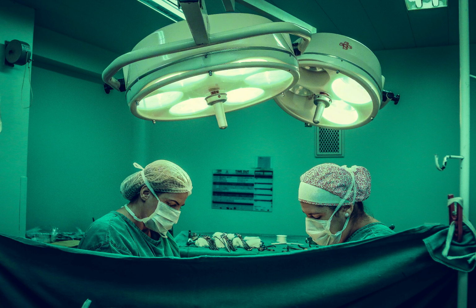Now here's the problem. Over time, repeated cleaning, handling, and sterilization can cause tiny cracks or pinholes in the insulation covering those laparoscopic instruments. Sometimes it's from harsh chemicals, rough handling, or wear and tear that comes with daily use. These small defects allow stray electrical current to leak out during surgery. That stray current can burn or damage nearby tissue without the surgeon even knowing it. These burns are often not visible through the laparoscope and may not be discovered until hours or days later, when the patient starts experiencing symptoms like abdominal pain, fever, or organ failure. Some insulation failures lead to complications such as bowel perforation, internal bleeding, sepsis, additional surgeries, and sadly, death.